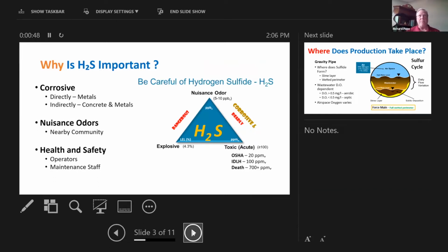Let me start off by saying, why is H2S so important? It has three tiers of importance to us in the odor industry. One, which we're going to talk about a lot more today, is corrosiveness. H2S is directly corrosive to metals, mostly ferrous and copper type metals, and indirectly corrosive to concrete and any other metals, including ferrous metals. It also is a nuisance odor. Communities complain about it all the time. And it's a health and safety issue for our operators and our maintenance staff.